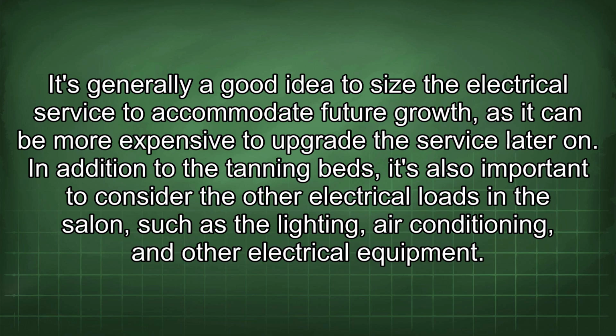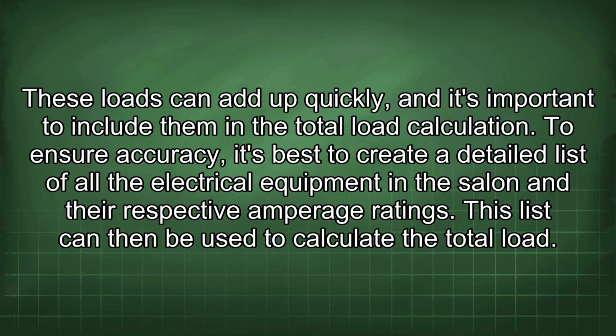In addition to the tanning beds, it's also important to consider the other electrical loads in the salon, such as the lighting, air conditioning, and other electrical equipment. These loads can add up quickly, and it's important to include them in the total load calculation. To ensure accuracy, it's best to create a detailed list of all the electrical equipment in the salon and their respective amperage ratings. This list can then be used to calculate the total load.